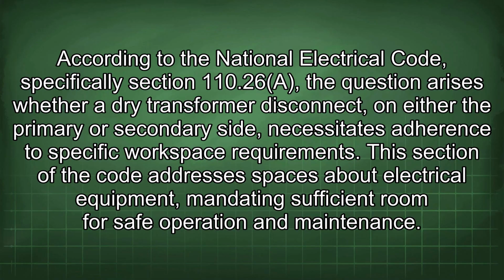According to the National Electrical Code, specifically Section 110.26(A), the question arises whether a dry transformer disconnect on either the primary or secondary side necessitates adherence to specific workspace requirements. This section of the code addresses spaces about electrical equipment, mandating sufficient room for safe operation and maintenance.